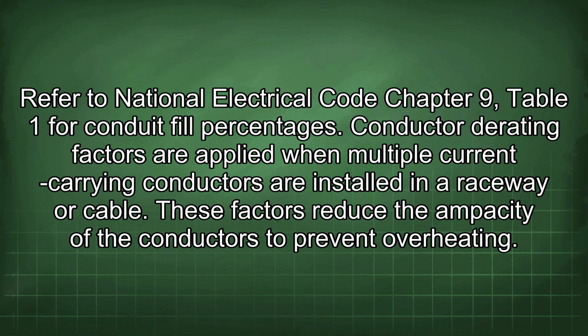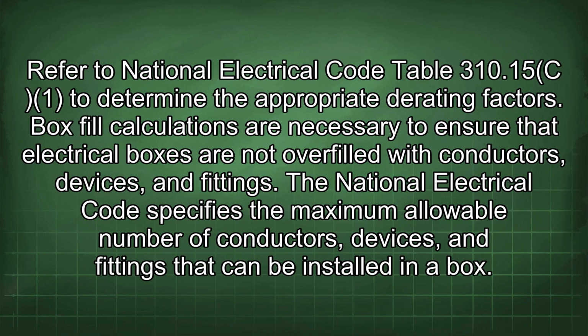Conductor derating factors are applied when multiple current-carrying conductors are installed in a raceway or cable. These factors reduce the ampacity of the conductors to prevent overheating. Refer to National Electrical Code Table 310.15 to determine the appropriate derating factors.